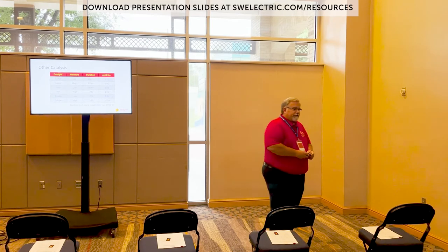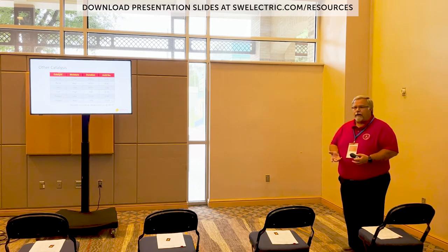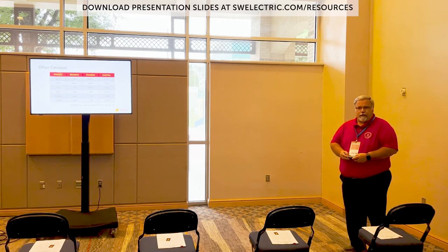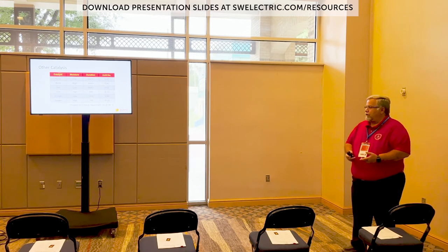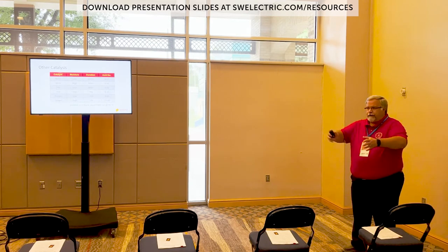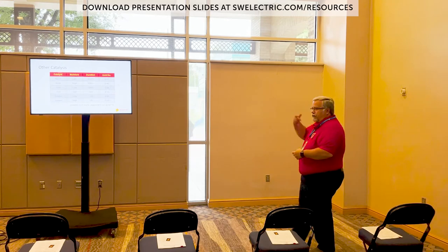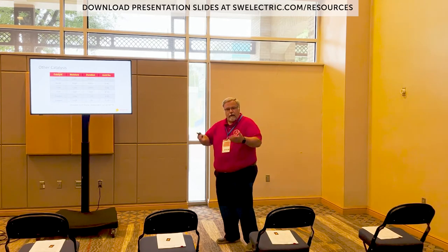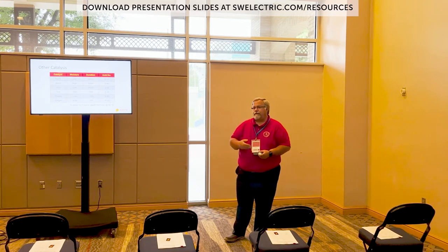So moisture nowadays is a very simple thing. We can get rid of that very easily by dehydrating it, pulling vacuum on the transformer if it's rated for vacuum. If it's not rated for vacuum, they have passive drying systems out there now that you can rent or buy. It's about the size of a refrigerator, and you just plug it in right next to the transformer, hook it up to the top and bottom valve, and you let it go. It does circulations, but it's a very slow, long drawn out process. It can be upwards of a year, depending on how big the transformer is and how wet it is, to dry it out. But the transformer doesn't have to go anywhere. It's still there, it's energized, so you're not losing any production or anything like that.